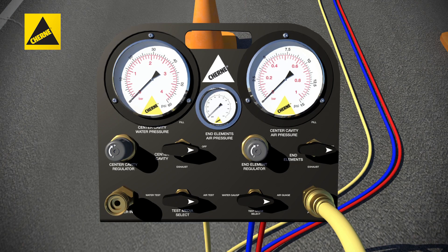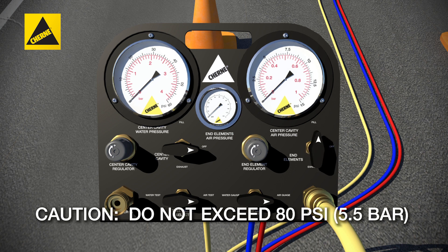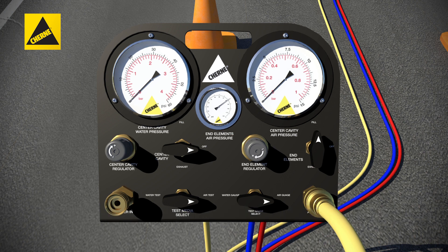Place the end element inflation valve in the fill position and adjust the end element regulator until 80 psi reads on the end element pressure gauge. Then place the end element three-way valve in the off position.